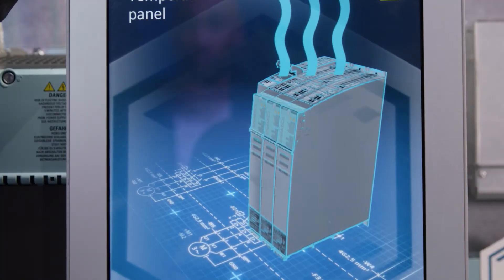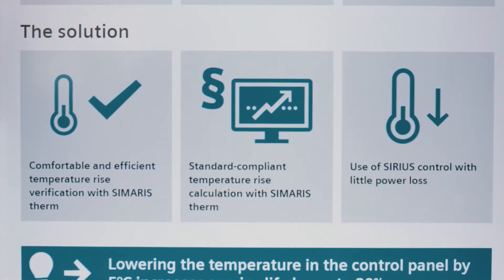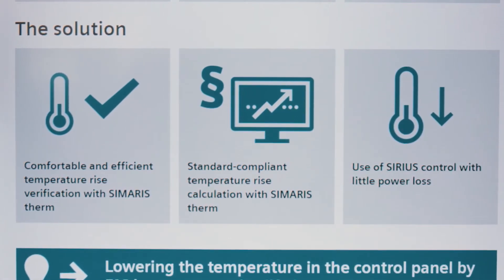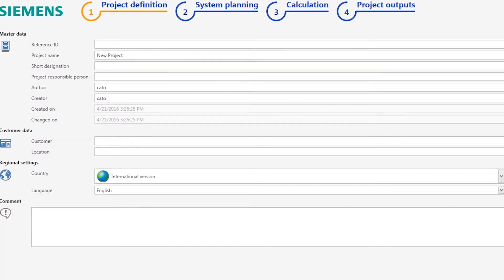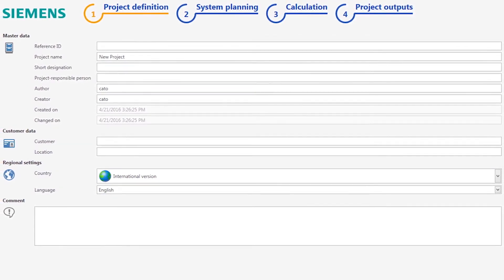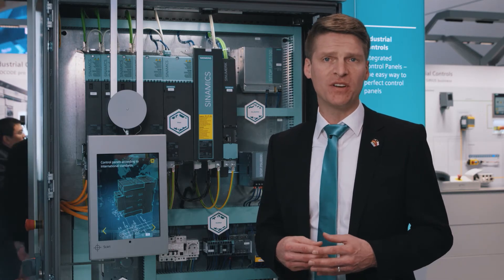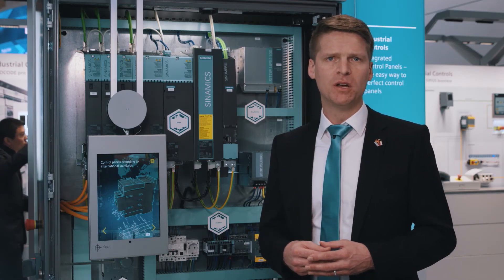Let's suppose you'd like to optimize the temperature rise concept of your control panel. Besides practical information on heat analysis, we offer you our free software, SIMARIS Therm. This standard-compliant solution allows you to calculate and document the temperature rise limits based on the power loss data of almost 30,000 Siemens products in just four steps.